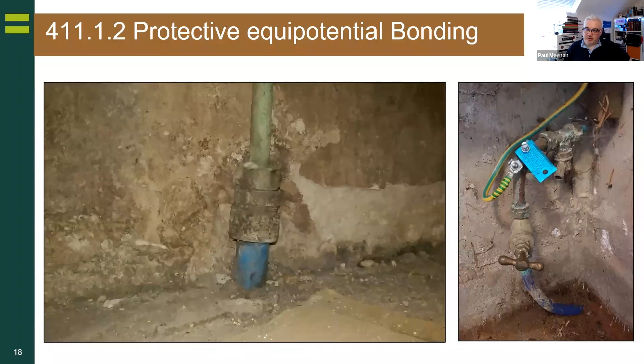Now, the regulation says, and there's a slight change, in brown underlined: in each installation within a building, extraneous conductive parts liable to introduce a dangerous potential difference. Now there's going to be a lot of debate on what a dangerous potential difference is, because if you go and get a clamp meter, you may find you have 3 or 4 or 5 volts sitting on your earthing system from other means or normal leakage.